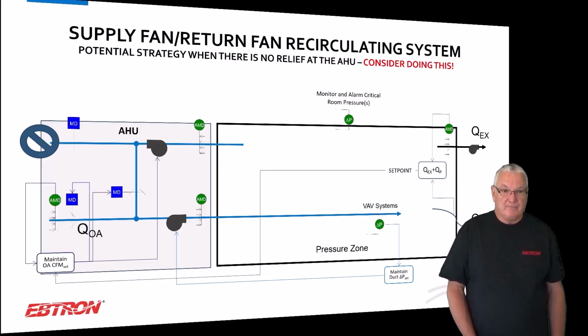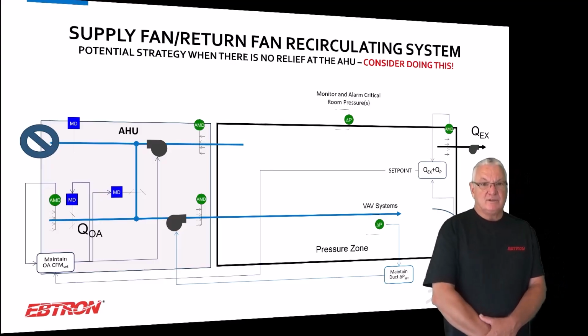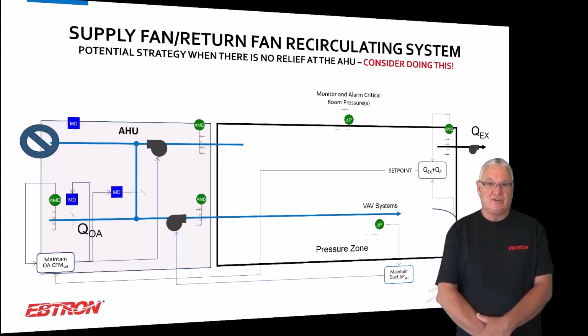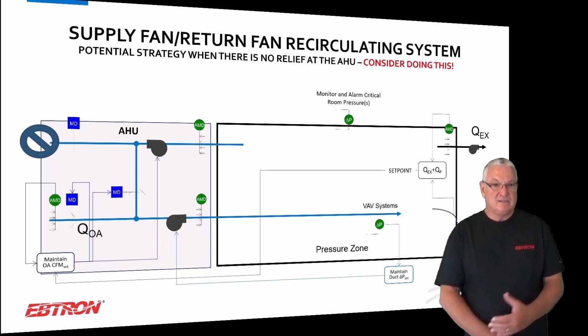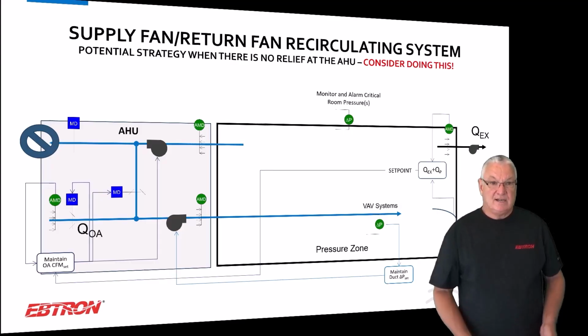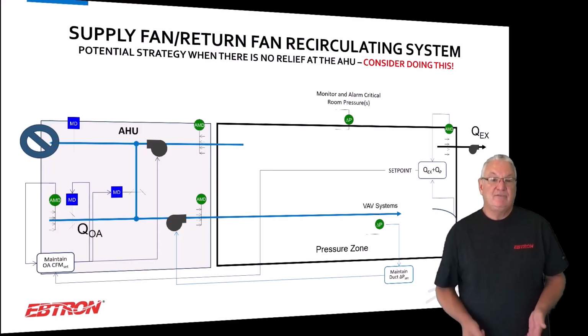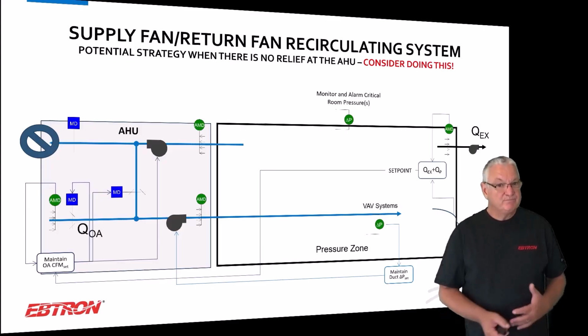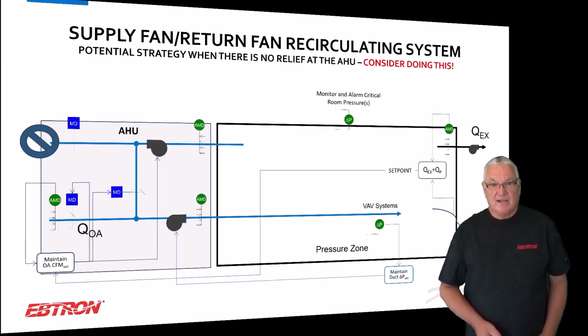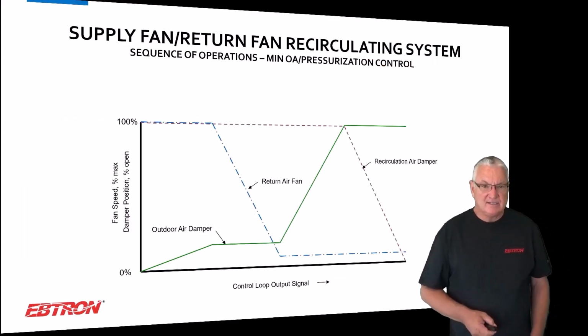And so, in fact, we're typically not even using the supply and return flow station. You would be using the supply airflow station if you were maintaining air changes, for instance, but not for the pressurization side of this. Like we said earlier, the outside airflow meter is inherently more accurate than the differential of the supply and return, even with good supply and return flow measurement. So we prefer to do this. And anyhow, what we're going to end up doing here is this sequence.